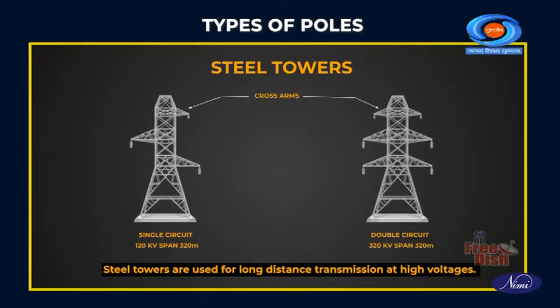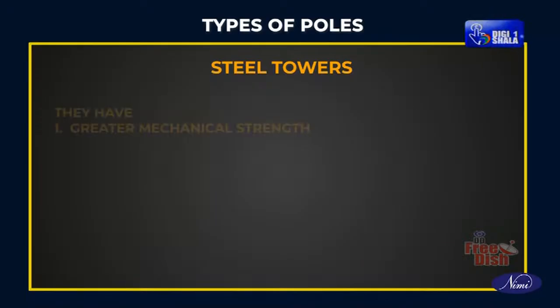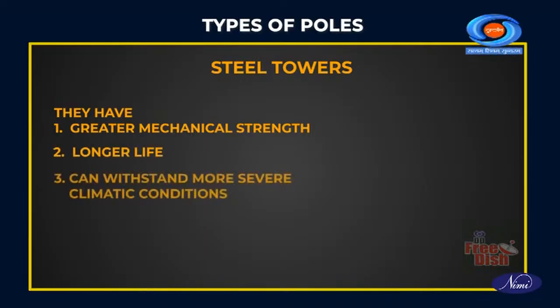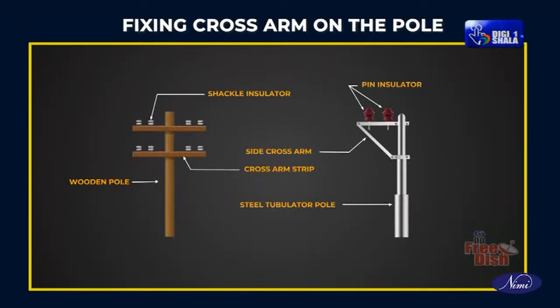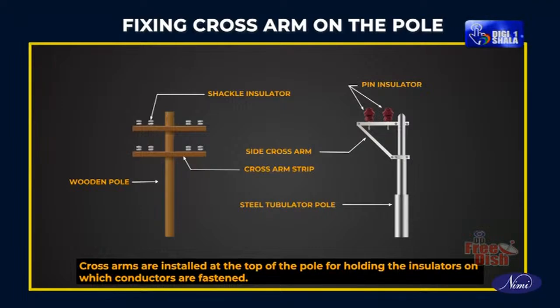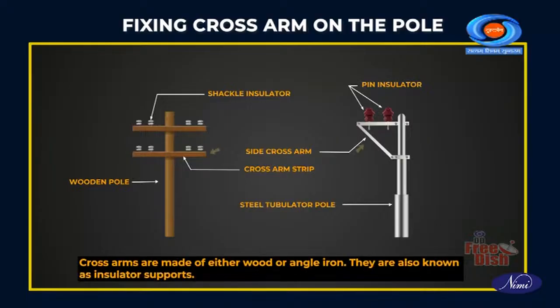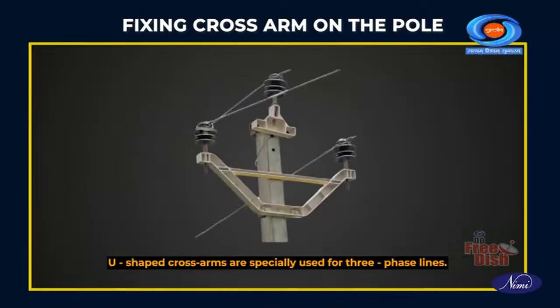Steel towers. Steel towers are used for long distance transmission at high voltages. They have greater mechanical strength, longer life and can withstand more severe climatic conditions. Fixing cross arm on the pole. Cross arms are installed at the top of the pole for holding the insulators on which conductors are fastened. Cross arms are made of either wood or angle iron. They are also known as insulator supports. U-shaped cross arms are specially used for 3-phase lines.